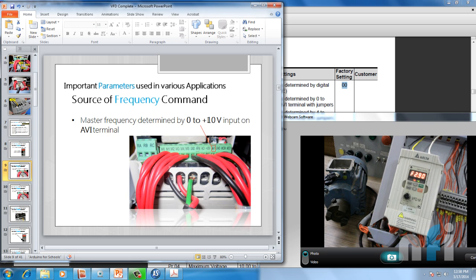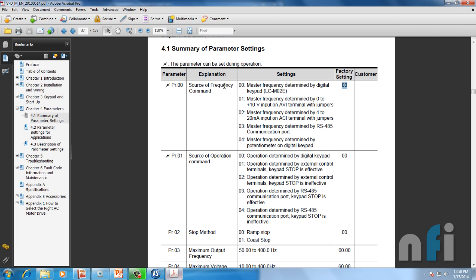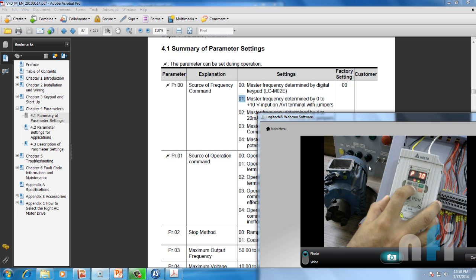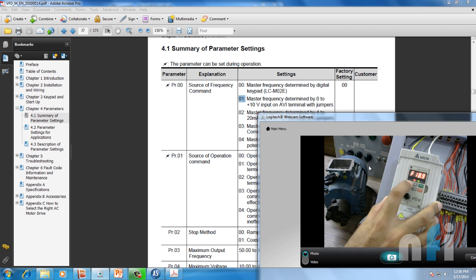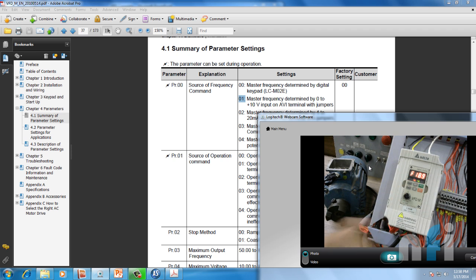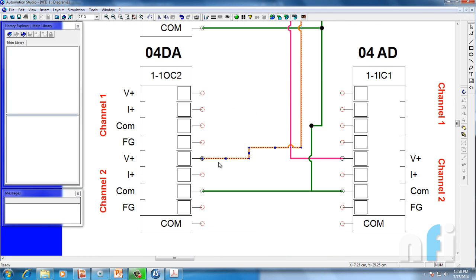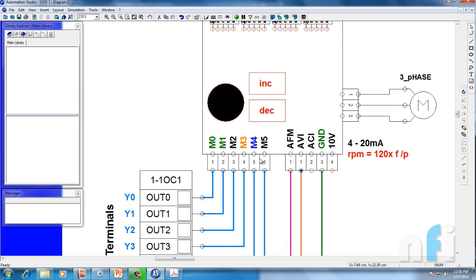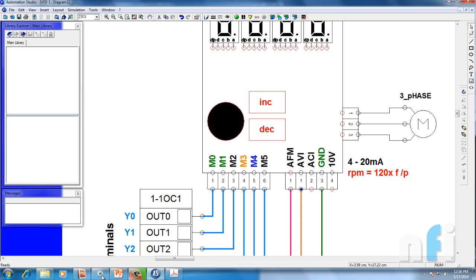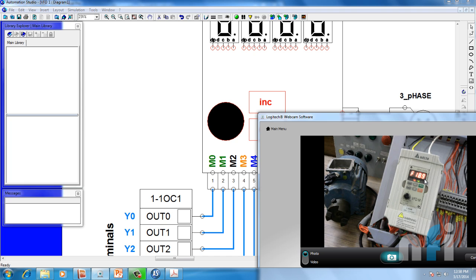The next command is master frequency determined by 0 to 10 volts on AVI terminal — that's the AVI terminal. Let's switch over to this mode. For parameter 00, we have to enter 01. If you see the frequency is 18.9 Hz — it is not controlled by the keypad anymore; it's getting the frequency from AVI. Going back, the AVI is connected to channel 2, and my card is supplying some voltage to this drive, which is forcing it to 18.9 Hz.